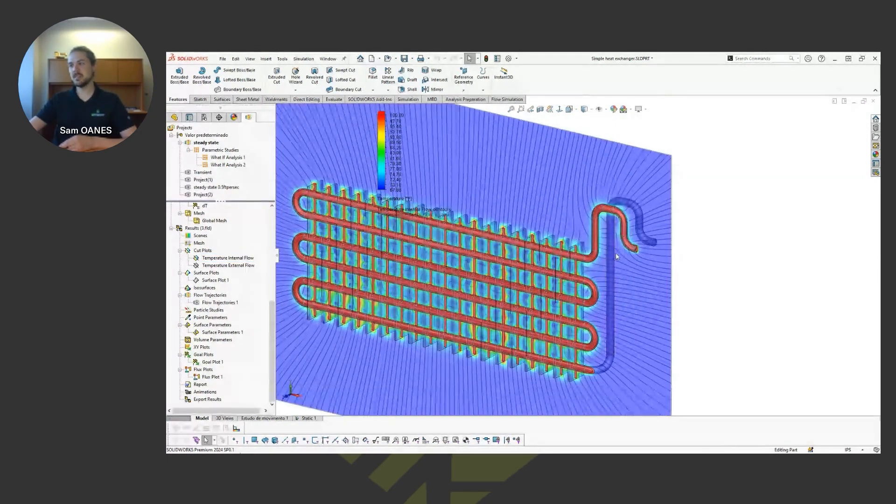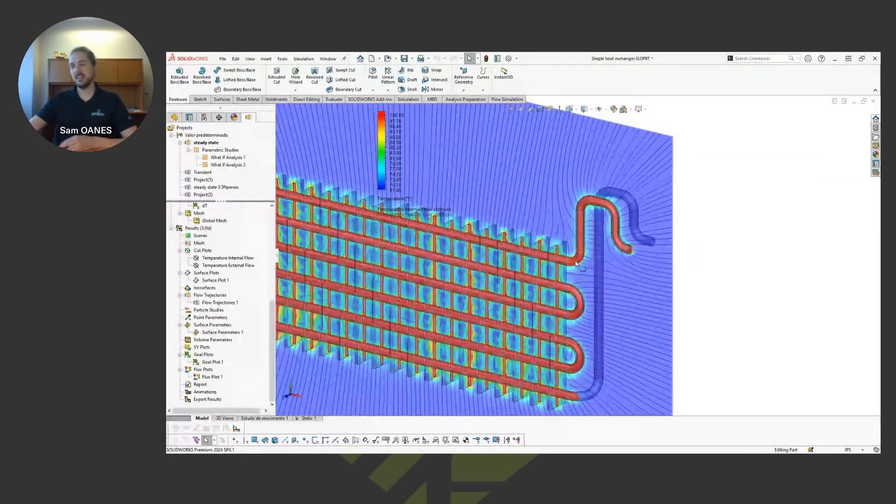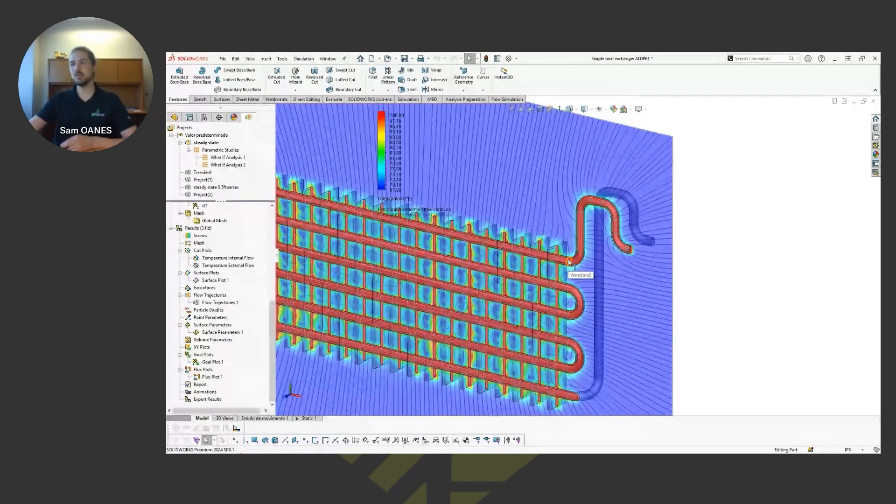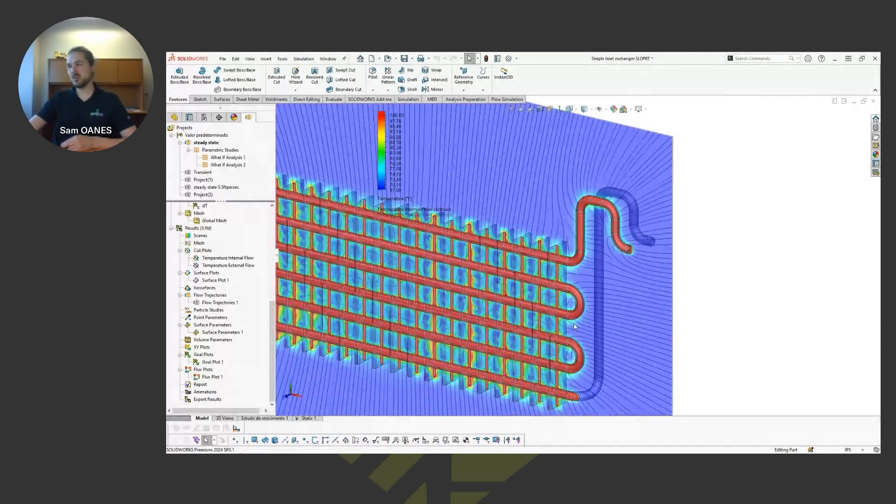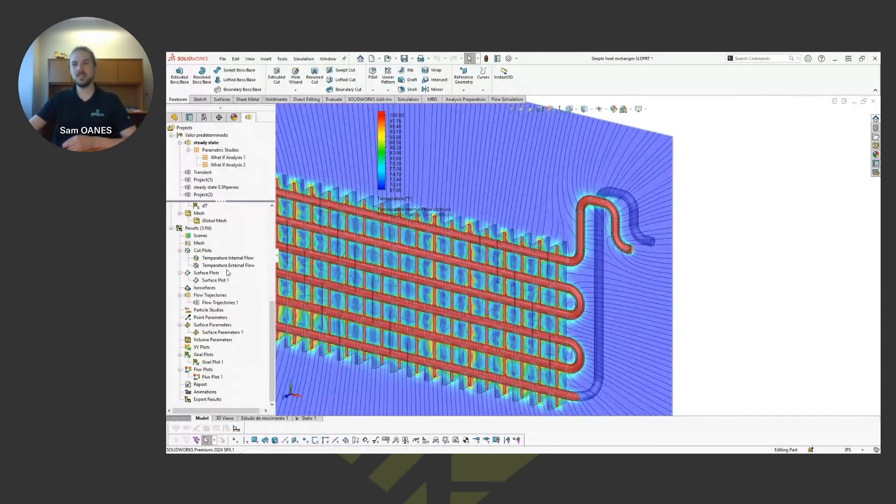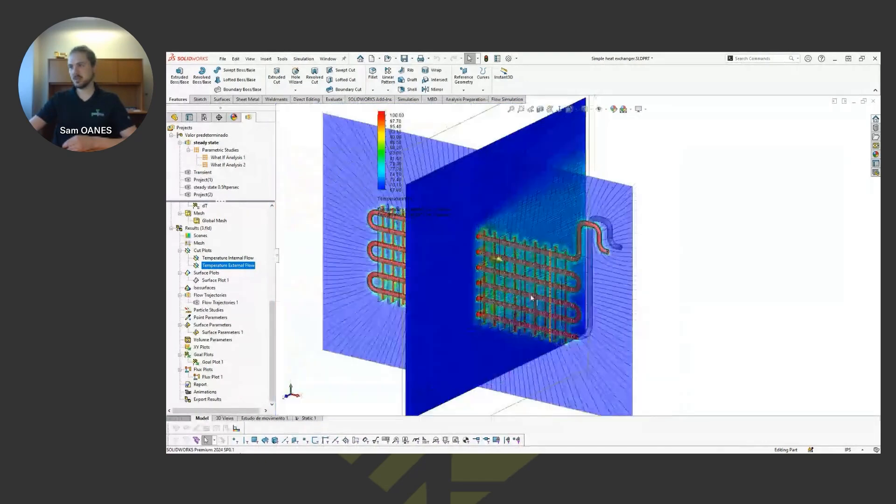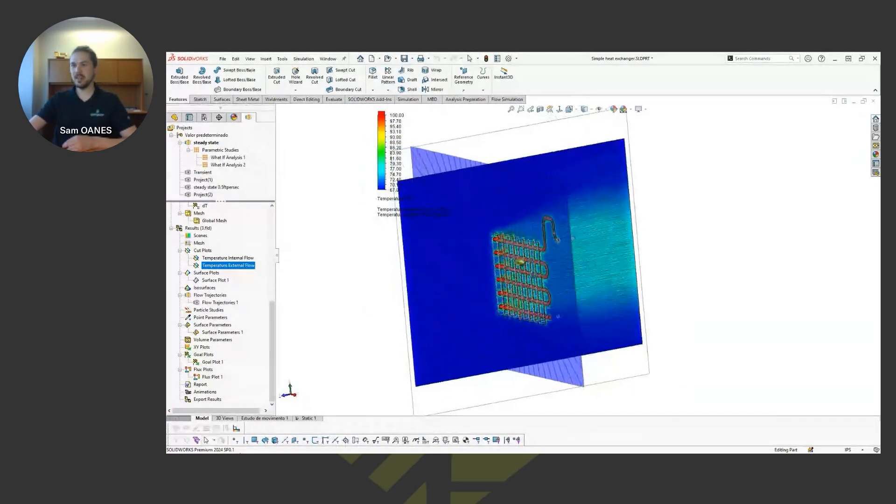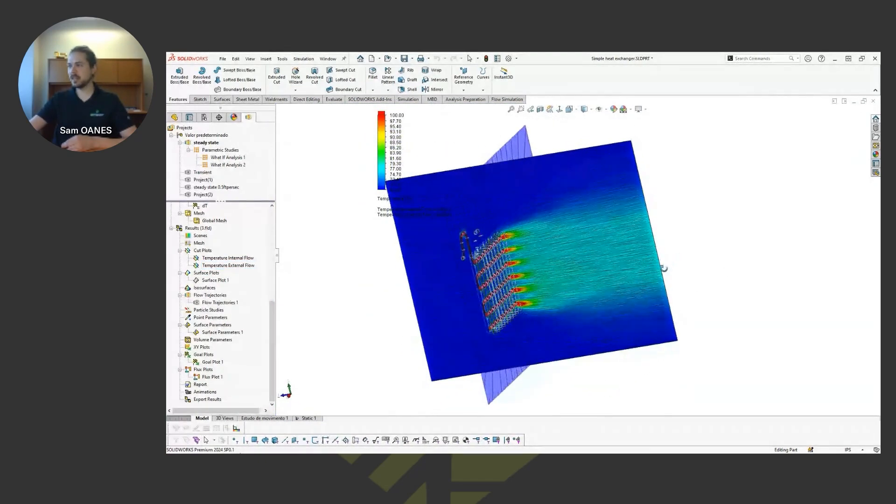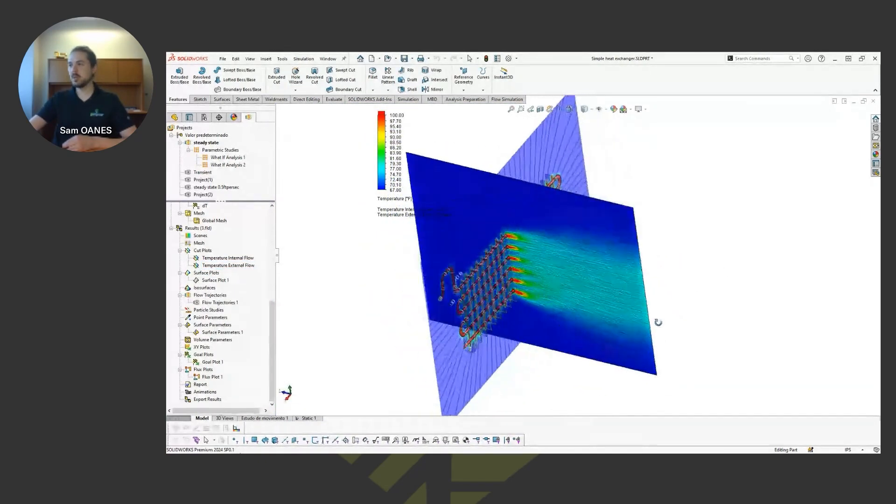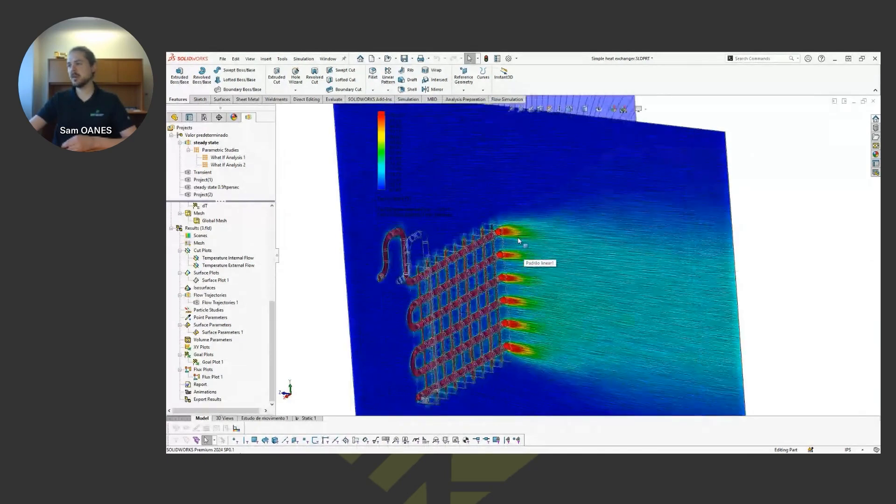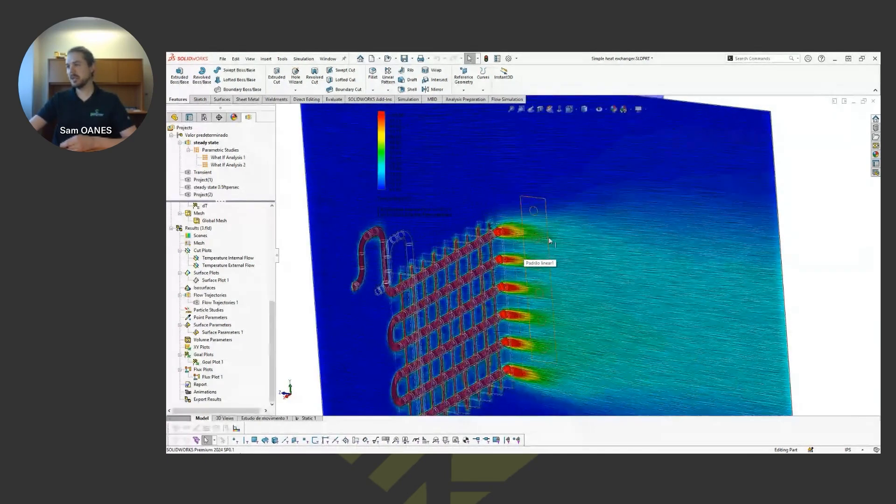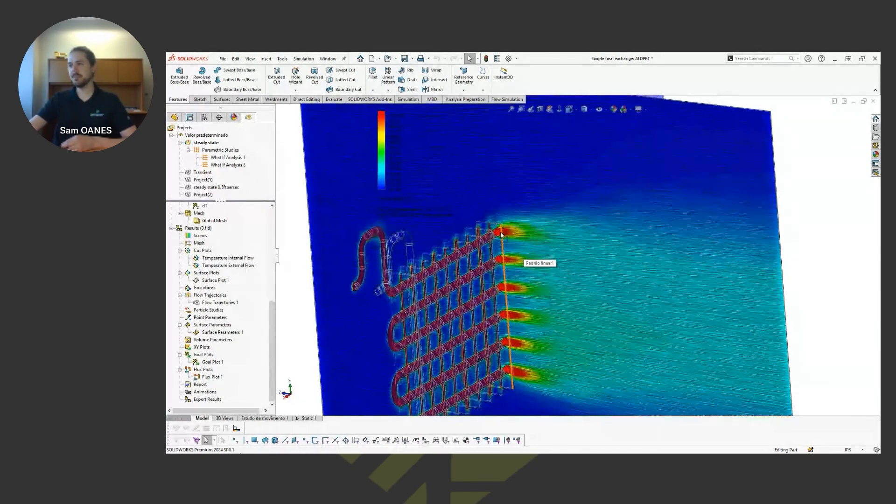But what happens here, we can see at the steady state solution we have a very uniform temperature gradient through that water flow. And if we want to take a closer look at the external flow, you can see how that wind load, that 50 miles an hour, is peeling that heat away from the copper pipe.